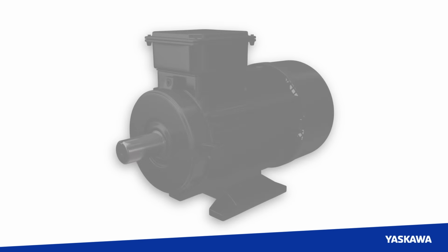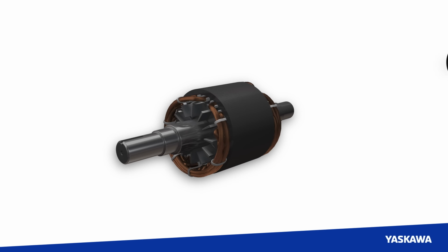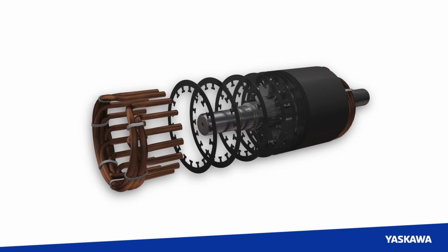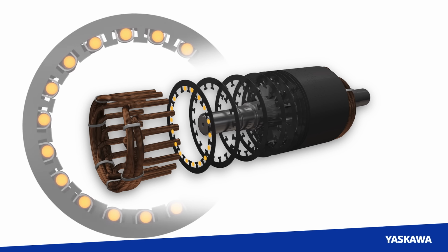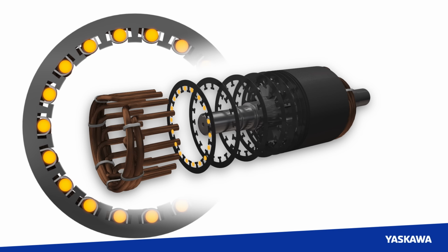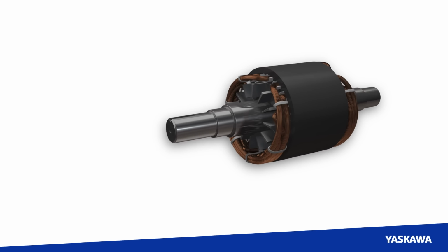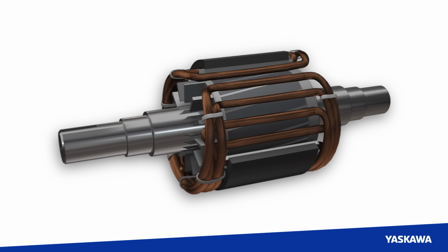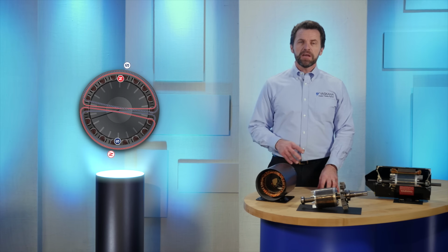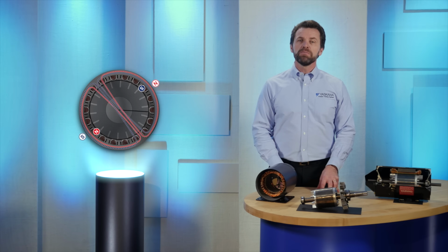As we described earlier, the stator has a core of individual plates that are laminated together. These plates have slots in them, which allow insulated electrical windings to pass through the core. The stator windings are distributed around the stator in such a way that when current flows through them, the stator produces a magnetic field. To better understand how the magnetic field is produced, think about the electromagnetic demonstration you may have seen back in science class.